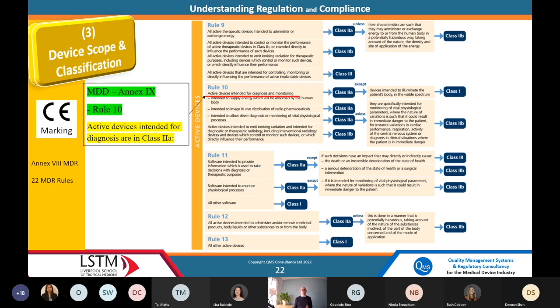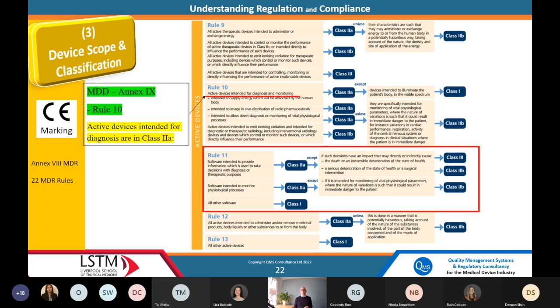And then there's this new rule that's been slotted in, Rule 11, and this is specifically for software. And this says software intended to provide information which is used to take decisions with diagnosis or therapeutic purposes. That would be a Class 2A, or software intended to monitor physiological processes, Class 2A. All other software, Class 1. But there won't be a lot that is all other software because of the wideness of that definition. What that means is that you're a minimum Class 2A, and if you look in the top right of that section, it says if such decisions have an impact that may directly or indirectly cause the death or irreversible deterioration of the state of health, you're a Class 3 device.